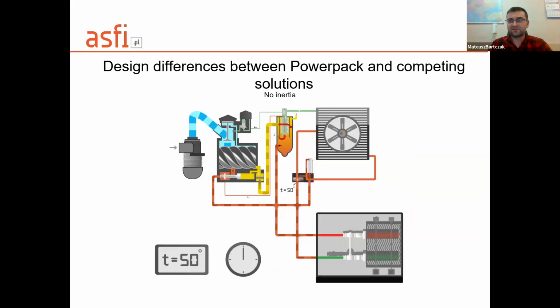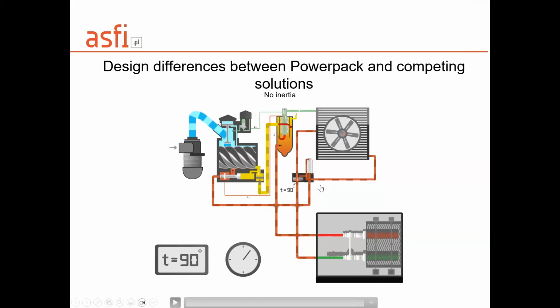Inertia, what kind of valve has no inertia? Only the kind which does not exist. In our solution, we don't use a three-way valve. We control the temperature of oil by controlling flow on the water side, and we keep the temperature of oil at the 55 degrees level. So we don't overcool it. We can flow the water when the water is warmer than the oil. So we control it. And in that case, the temperature near the valve near the radiator is the same as in the separator, with 1 second delay.